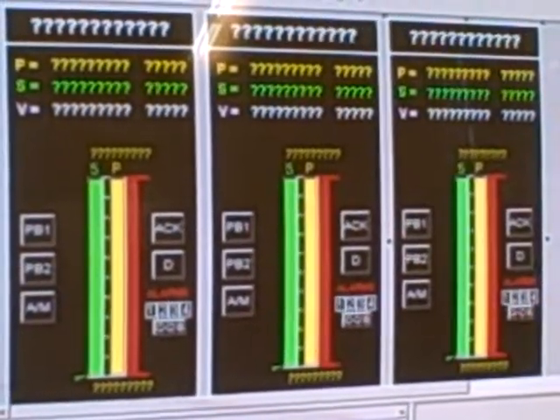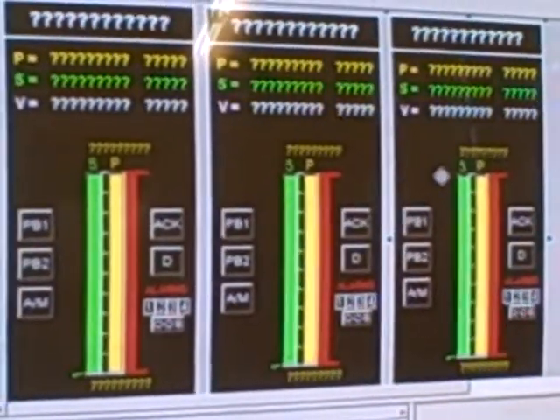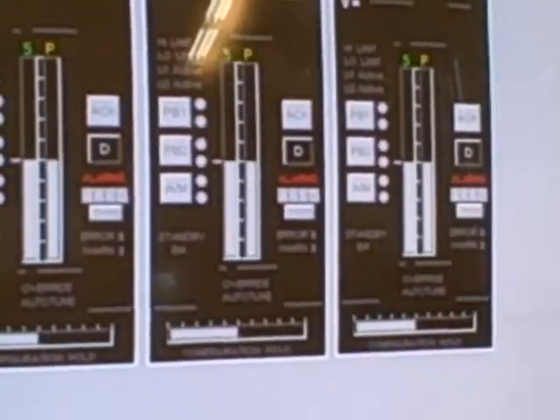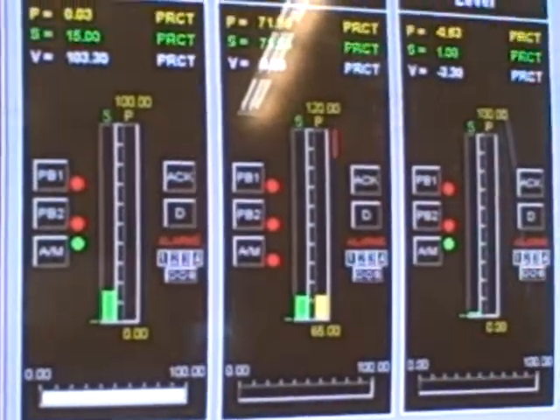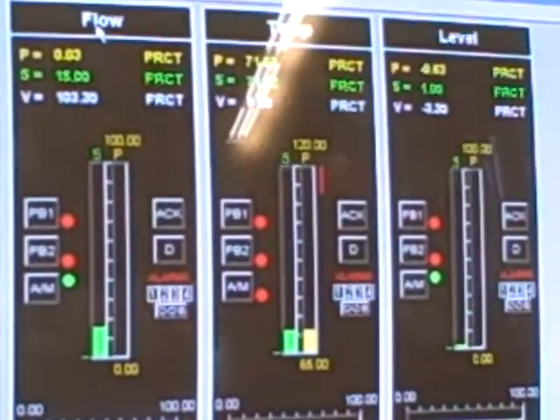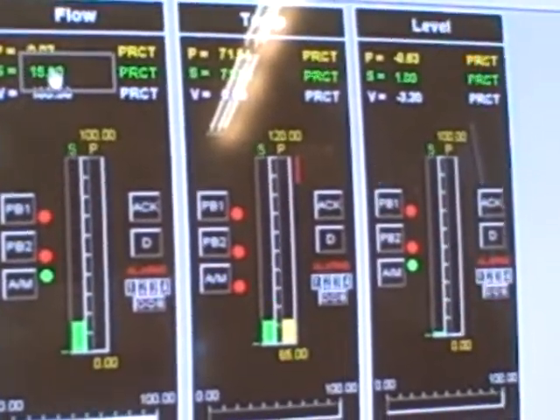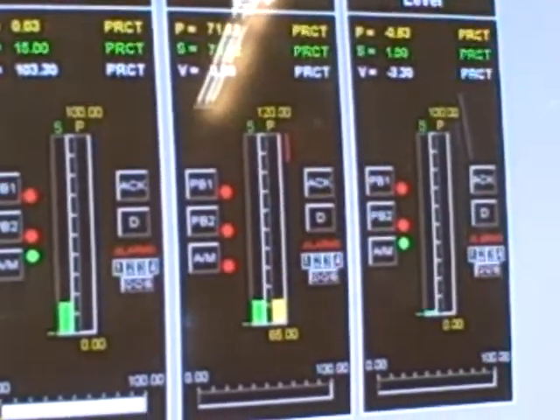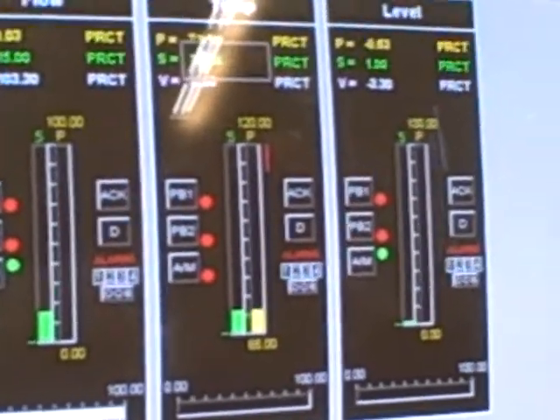So when I go to Runtime, I ought to see displays that correspond to my actual physical variables on those controllers. I click the Runtime button, and we see this is the screen the operators will actually be looking at under normal circumstances. It's going to take some time to grab the data. Flow is now measuring zero flow, set point of 15, valve wide open. Temperature is measuring room temperature right now, 71.54 degrees.